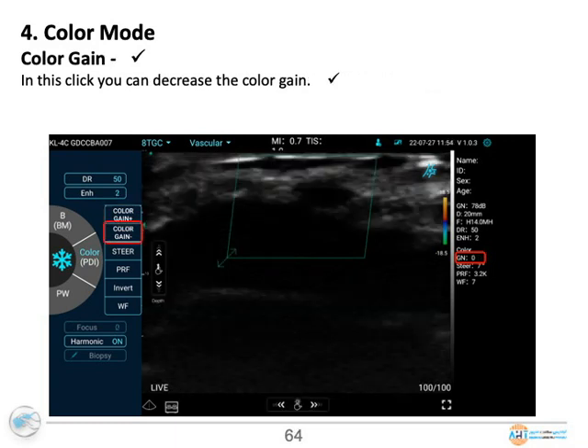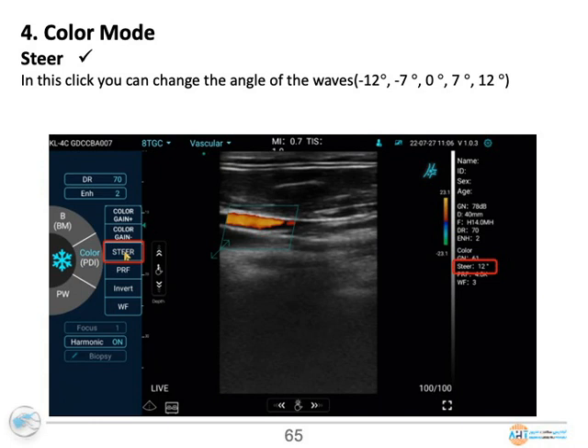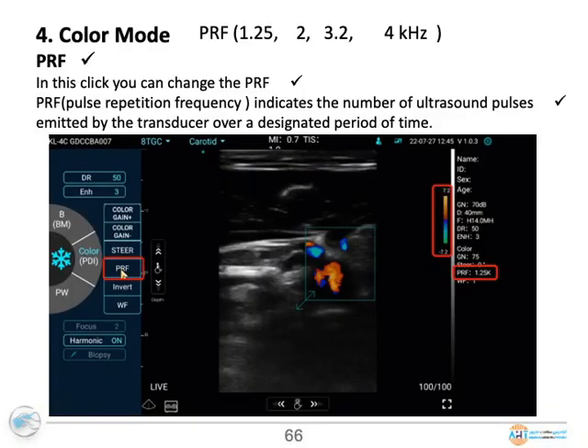Color mode, color gain minus. In this click, you can decrease the color gain. Color mode, steer. In this click, you can change the angle of the waves, minus 12 degrees, minus 7 degrees, 0 degrees, 7 degrees, and 12 degrees. Color mode, PRF. In this click, you can change the PRF. PRF, pulse repetition frequency, indicates the number of ultrasound pulses emitted by the transducer over a designated period of time.